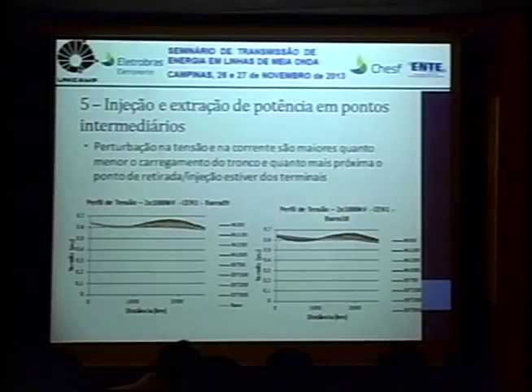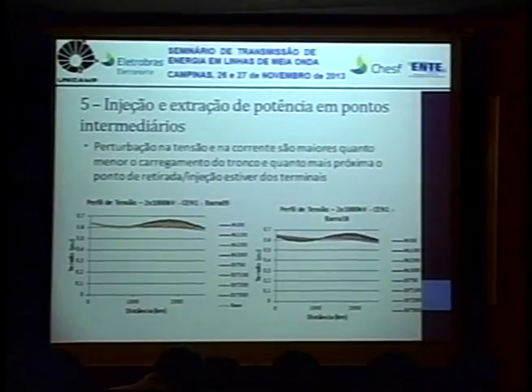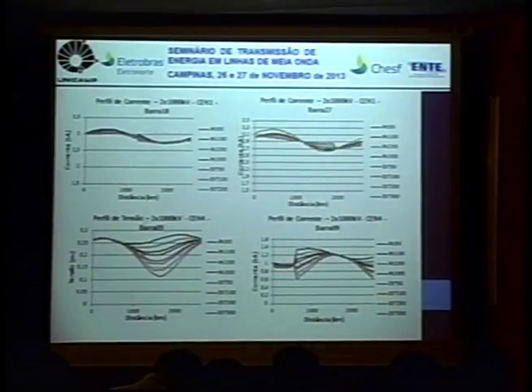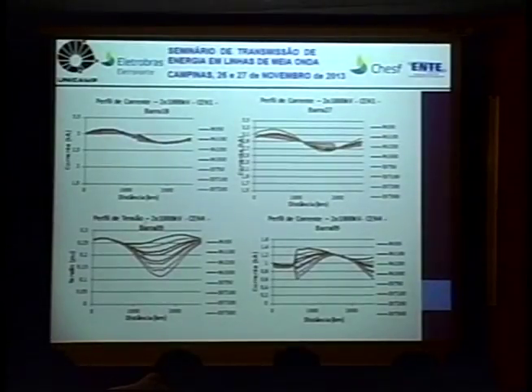This is in the middle of the line. When I put it in the middle of the line, an extraction from 0 to 300, this is for scenario number 1, a scenario of high generation in Belo Monte and a lot of transmission in the link. When there's a lot of power being transmitted in the link, if I do this extraction, I don't see a lot of change in the voltage profile in the line. So this means that it did not move far from the characteristic power. In the current profile, it's the same thing. There's not much change because the line is in that scenario of high load.